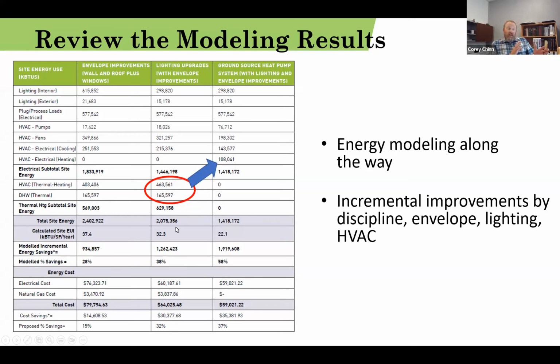Now, remember, our baseline building is gas and electric, and we're looking at energy savings, but we also have to look at cost savings. So in order to get our HVAC systems over the hump to both save energy and dollars, we have to look at something less than traditional. So our baseline building was boilers and VAV reheat. We look at switching that over to all electric, no on-site combustion.